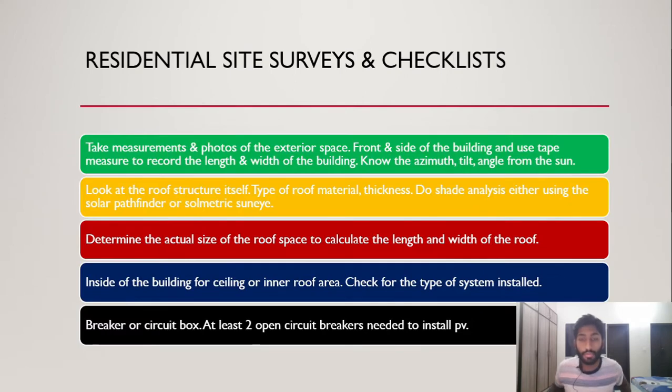When it comes to site surveys or residential checklists, there's some key things you need to do. First is take measurements and photos of the area and surrounding buildings - front side, back side - just to have a good idea. Use a tape measure to record the length and width of the roof space to know how long it will take to accommodate solar panel installation. Know the azimuth angle and direction that the roof is facing, whether it's 180 degrees or 170 degrees. Based on that you can also calculate the tilt angle from the sun.